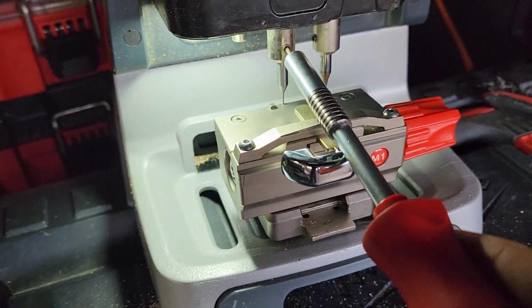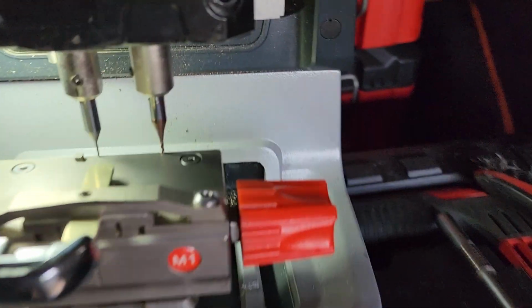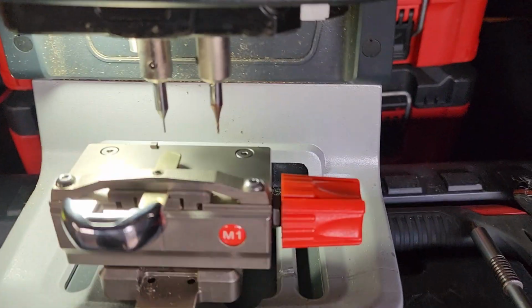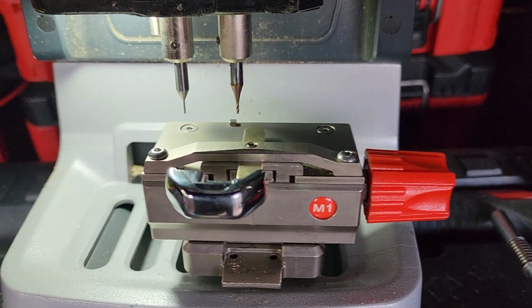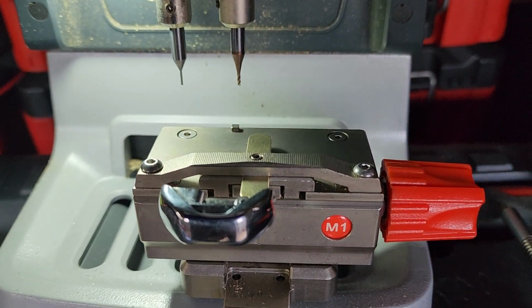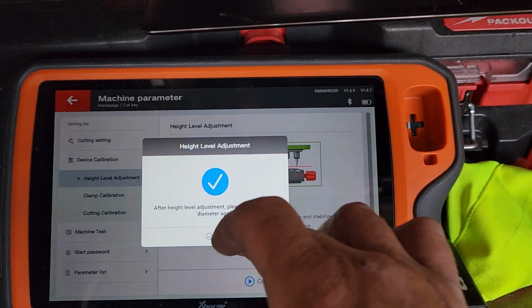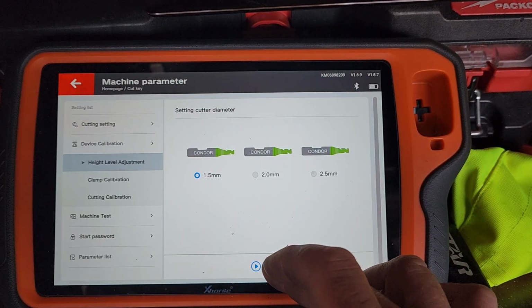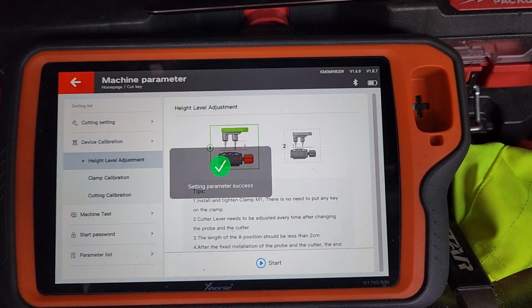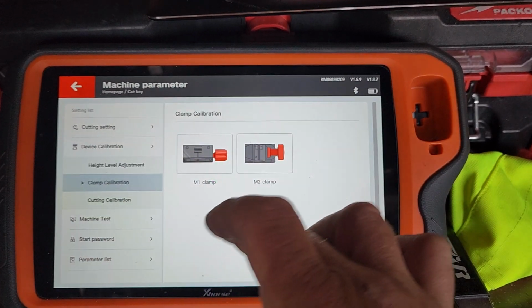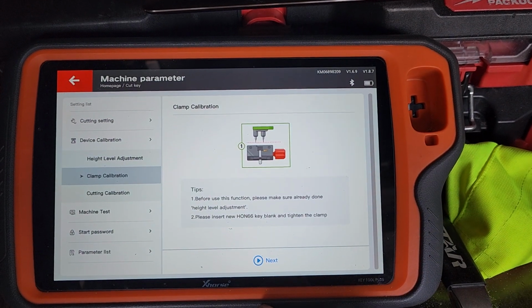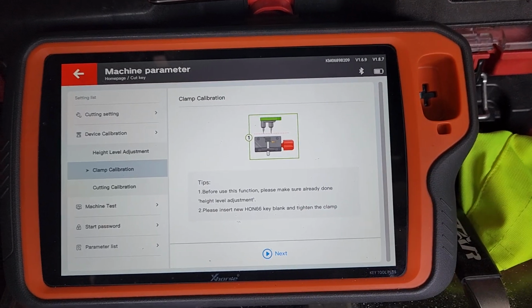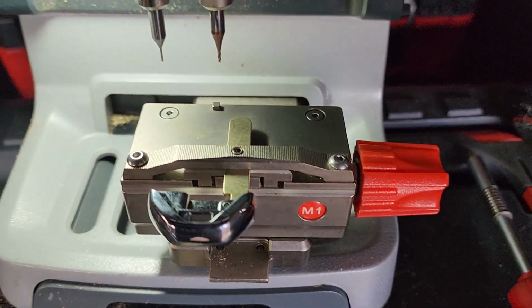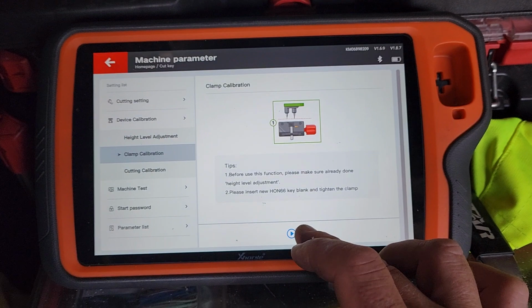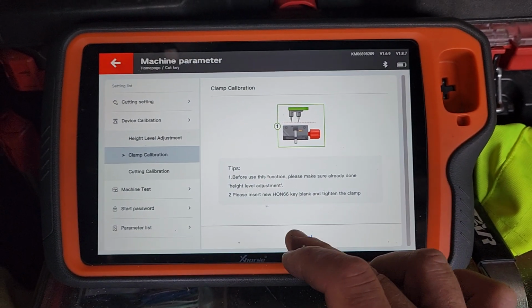You heard it drop. Now the probe's touching the clamp. The cutter's touching the clamp. What's it going to do now? It's going to test that probe height, cutter height. If it's the same, it's going to say complete, which it is. Always asks us to make sure that we're done. Clamp calibration, M1, new HON 66. I already got the HON 66 in there. It's the same one that I used on the M5. I just flipped it over in case those two little notches matter.